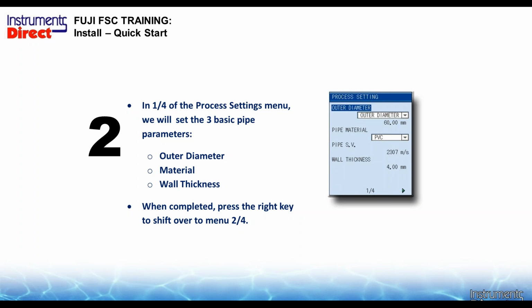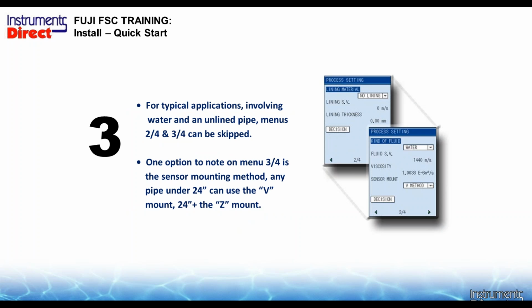Then we have a drop-down box to put in the pipe material. There's a whole bunch of different materials there. You don't need to put the material sound speed in unless you had an exotic pipe. In most cases, you're going to select PVC, copper, carbon steel, whatever, through the drop-down menu. And then we'll put in the wall thickness. Again, use the ANSI pipe chart book unless you have a testing tool. Then we move forward here.